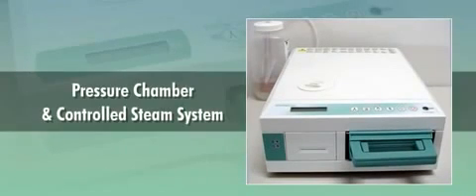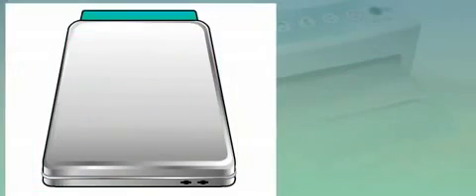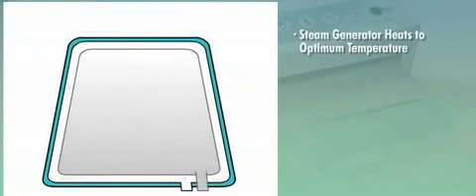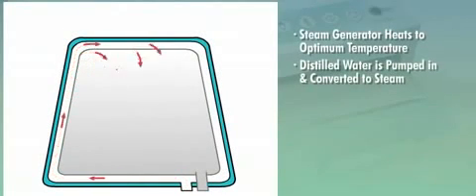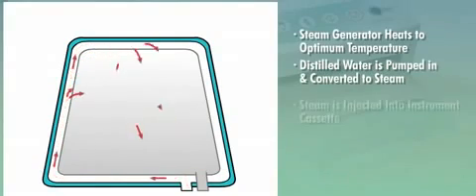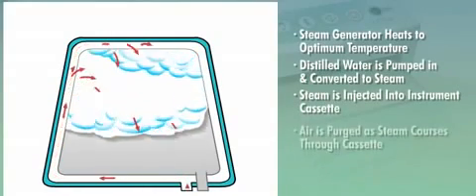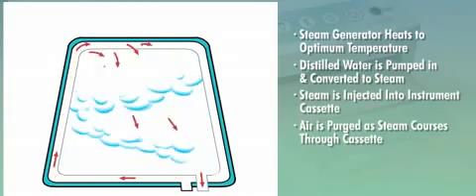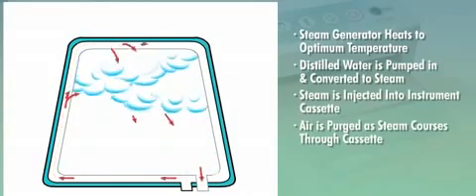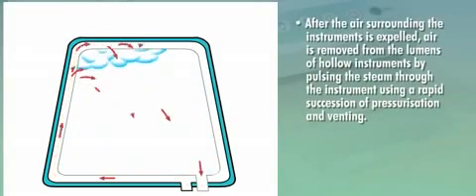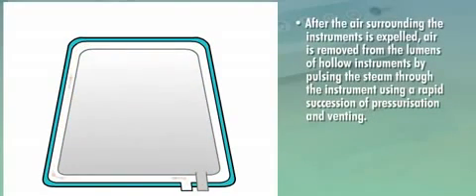The key to the STATIM's fast sterilization is in the unique design of the pressure chamber and controlled steam system. No water chamber needs to be heated, saving valuable time. When start is pressed, the steam generator heats to the optimum temperature and distilled water is pumped in and converted to steam. A wall of steam is then injected into the instrument cassette. Air is purged safely as the steam courses through the cassette and is expelled into a condenser bottle. After the air surrounding the instruments is expelled, air is removed from the lumens of hollow instruments by pulsing the steam through the instrument using a rapid succession of pressurization and venting.